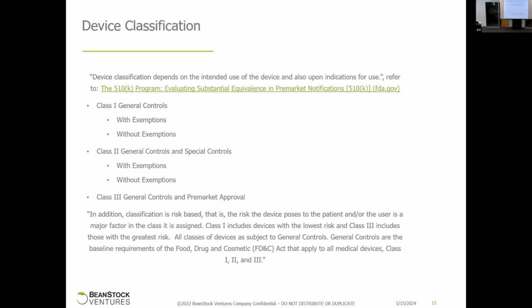So the device classifications, there's three. There's class 1, which is general controls with and without exemptions. There's class 2 with special controls with and without exemptions. And then there's class 3, general controls and pre-market approval. So you can read here that the classification is risk-based. So class 1 is the lowest risk.